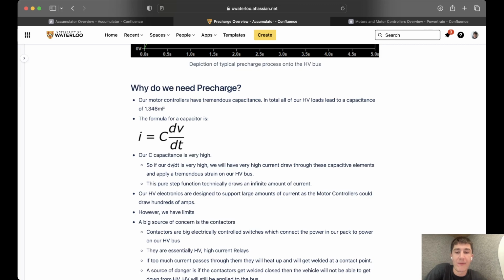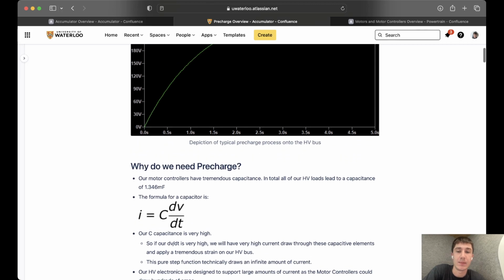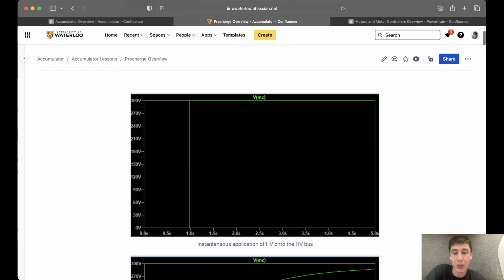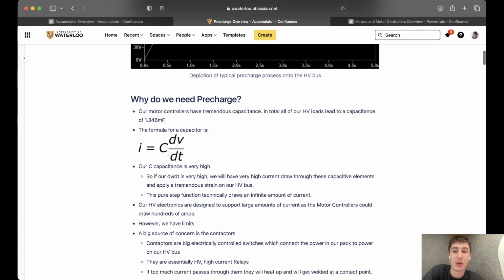So we have our very high capacitance, 1.3 millifarads is very high. Typically, capacitance is referred to in the pico, nano, and microfarad range. We also have a very high dV over dt. If we were to instantaneously apply the voltage, our dV over dt would be very high, nearly infinite, which would produce a nearly infinite instantaneous current. That's very bad and can cause tremendous strain on our high voltage bus. It can pop our fuses and break multiple components along the way.